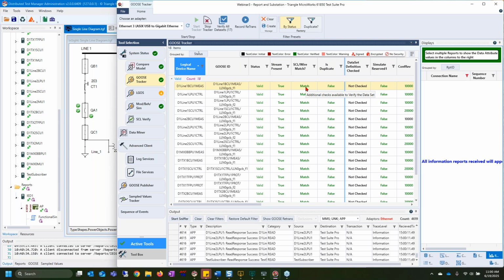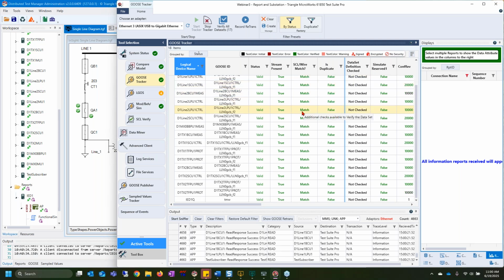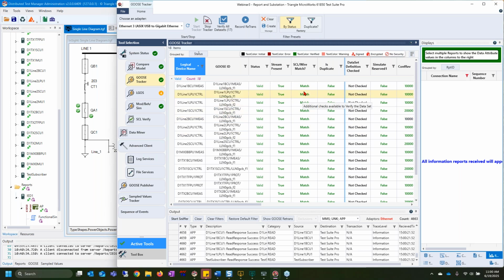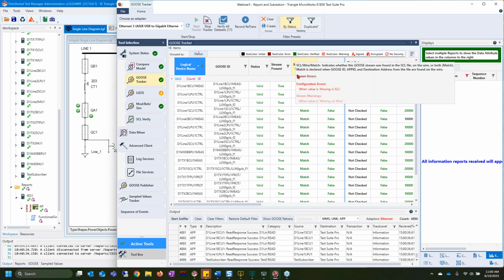And what that means is we want to make sure that the GOOSE that we're seeing is appropriate for what we provided TSP. So right now, everything says match. That means it's good. That means I told TSP I should see these 18 streams, and then we found those 18 streams. Everything's good. There are at least two different possible errors or warnings you can get from this.